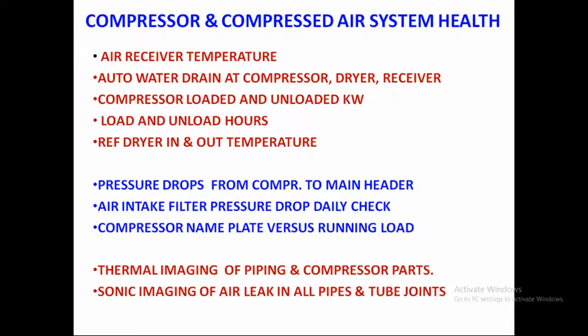That is why, in fact, I have been discussing monitoring of the compressor receiver temperature, the water drain at the receiver, the load unload hours, and the refrigerant dryer inlet and outlet temperature. The dryer output should be ambient temperature plus 5 degrees, or ambient temperature minus 5 degrees. For pressure drops, you have your pressure switches or a pressure gauge and an indicator. Thanks to IoT, incorporate IoT devices end to end on all the main headers and on the tail ends where the heavy withdrawal is. When there is a heavy drop of pressure, it means there is a leakage happening. Unwanted leakage is happening, and that can be corrected.